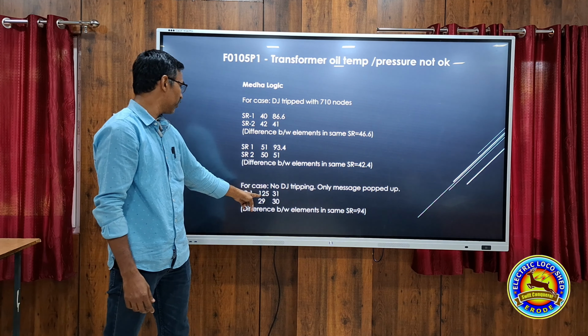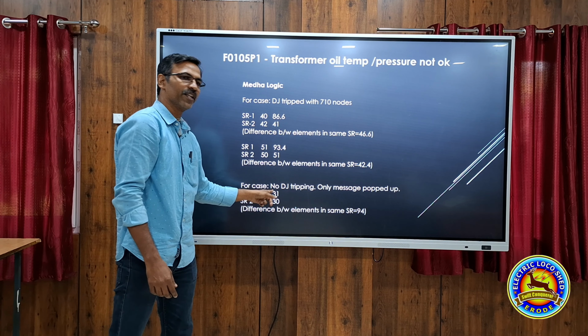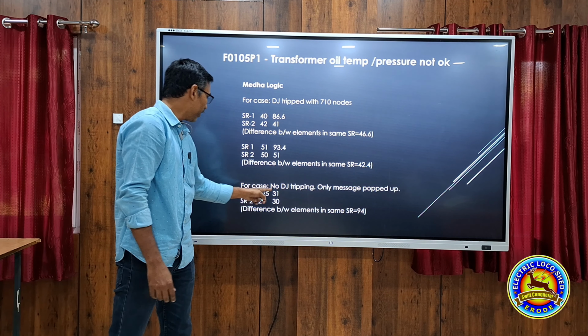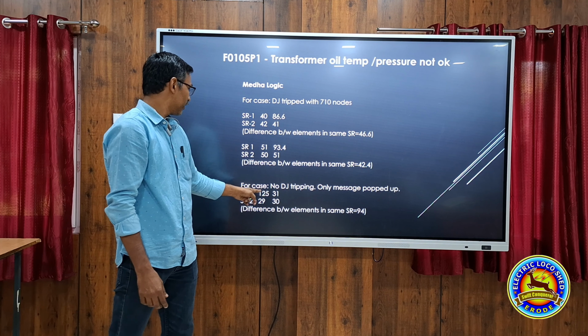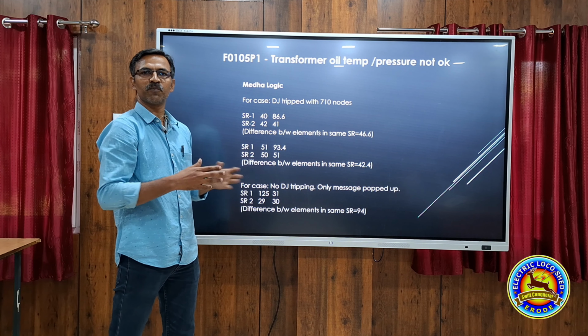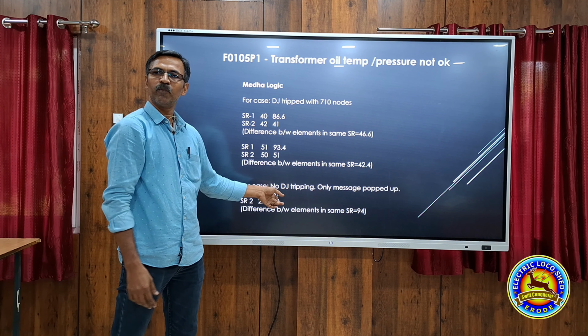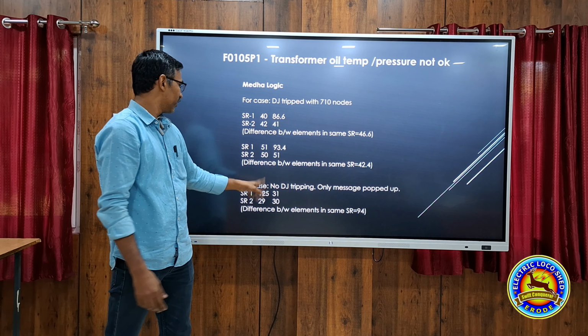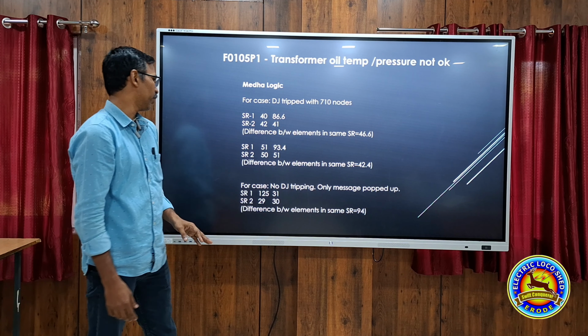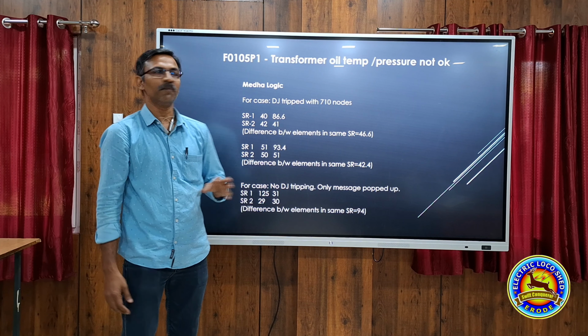In that sensor combination, of both elements only 31 will be taken, because this is a very huge difference, more than 50. So the lower value will be taken for DJ tripping. So in this case, DJ will not trip, but one pop-up message will come.